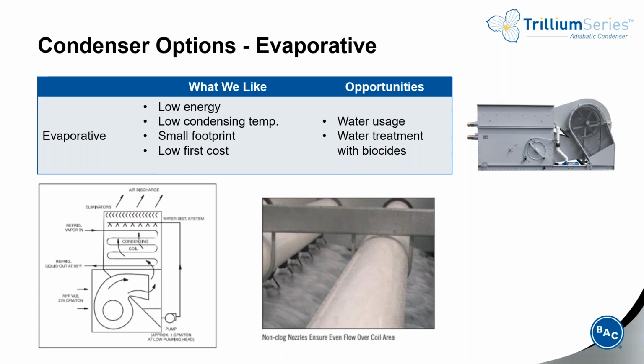And for this reason, most evaporative condensers are allowed to design for condensing temperatures around 95 degrees or sometimes even lower. These lower condensing temperatures mean smaller compressors, lower compressor energy. And using the evaporative cooling effect of water means we need less air volume, so smaller fan energy, less surface area, a smaller coil, which translates into a smaller footprint.